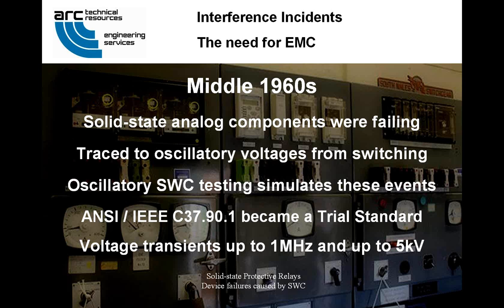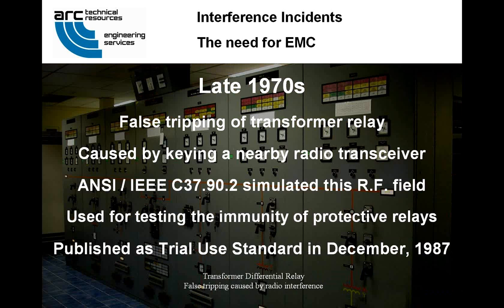In the late 70s, the false tripping of a transformer differential protective relay knocked a 380 megawatt steam turbine generator offline. It was caused by an employee keying a portable radio transceiver less than a meter from a protective relay rack. ANSI IEEE C37.90.2 simulated this radiated RF field for testing immunity of protective relays to this threat, and it was published as a trial use standard in December of '87, at only 10 volts per meter with AM modulation. The guy backed into the rack with the radio in his pocket, I was told.